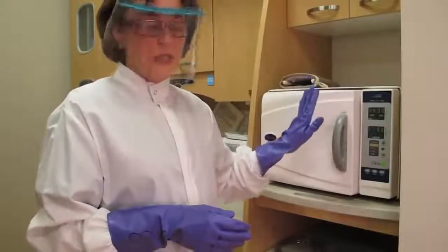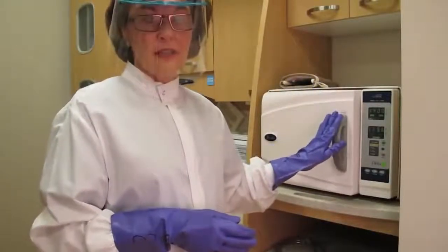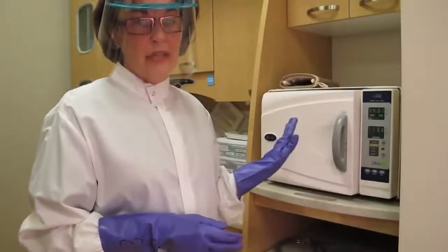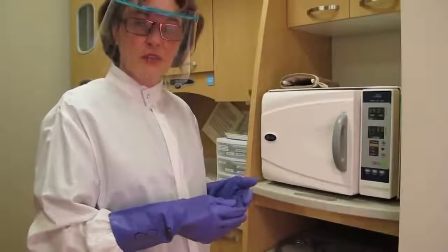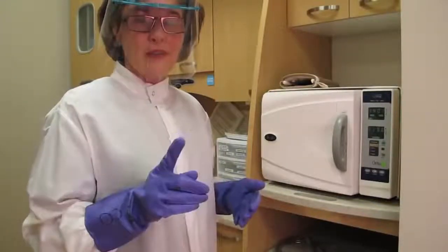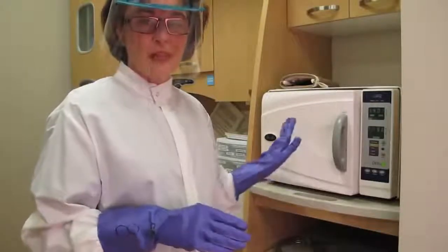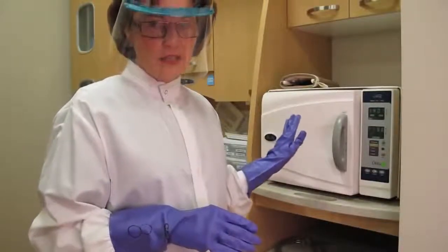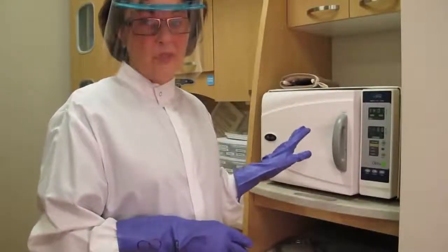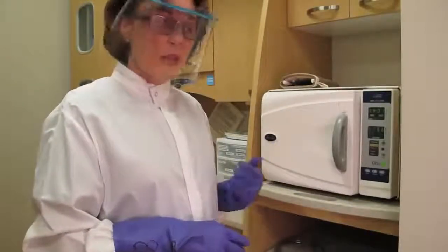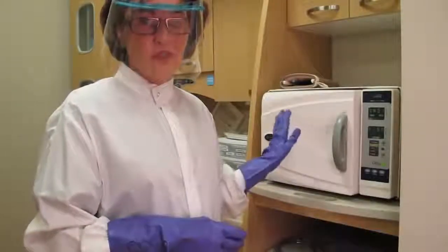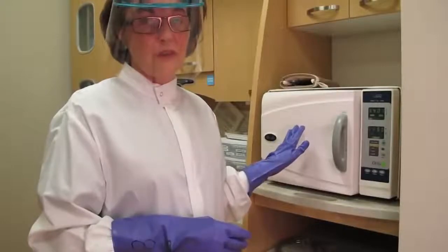Make sure that the sterilizer is working correctly and that you're monitoring it with biological monitoring, as well as using pouches that have indicators on them that show when the instruments have been sterilized. One more thing, it's really important to write down the date that you sterilize the instruments, the cycle, and which sterilizer if you have more than one. That way, if you come up with a failed biological monitoring, you know for sure which instruments were involved in that.